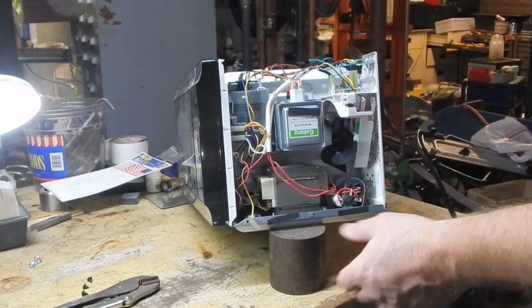Another possibility is if there's any kind of surge protection device — if this was hit by a power surge and there's a metal oxide varistor somewhere on one of these PC boards that was supposed to absorb the energy of the surge, sacrificing itself to save whatever else. If that device exists here and has taken the brunt of the power surge, which we don't even know happened, well then that could be the culprit too.